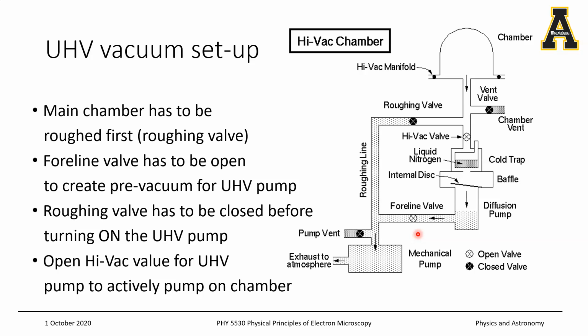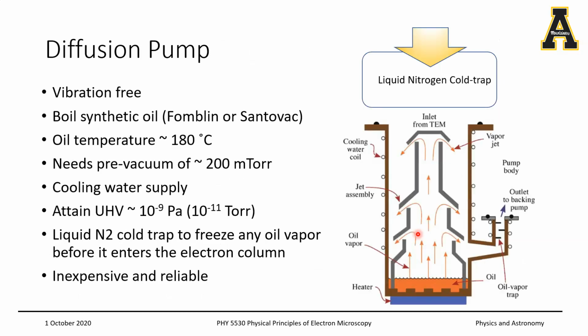Okay. All right, let's look at what diffusion pumps are. Diffusion pumps are very commonly used in ultra high vacuum systems for XPS or AES or even in TEMs. And the main reason for that is it is a vibration-free technique. So you don't have any vibrations whatsoever.